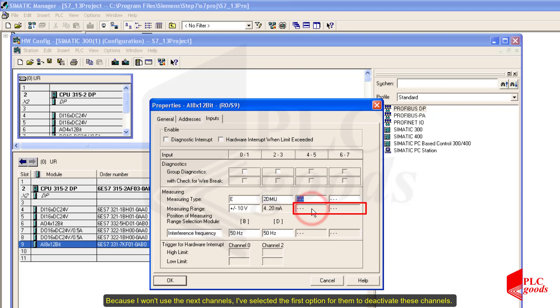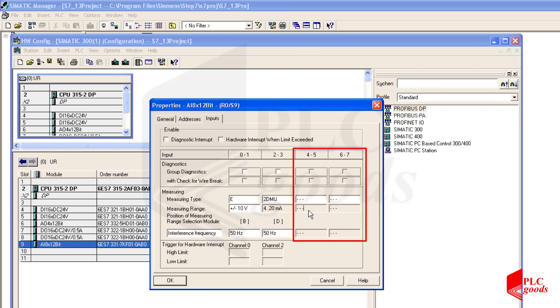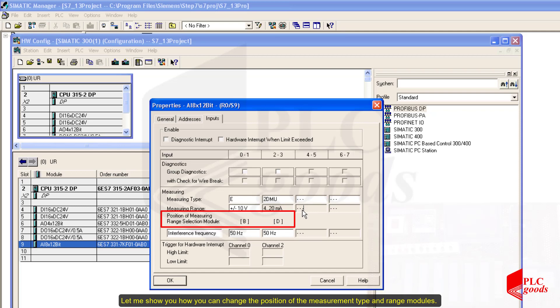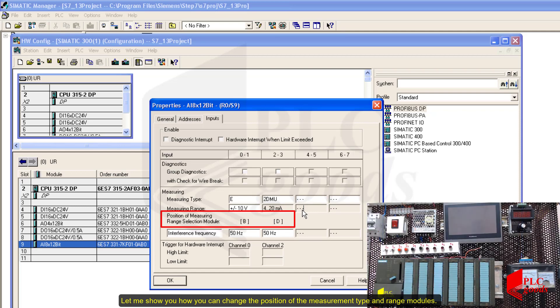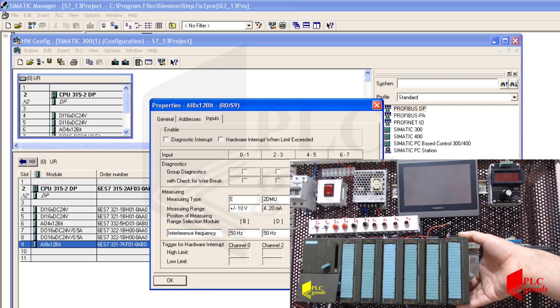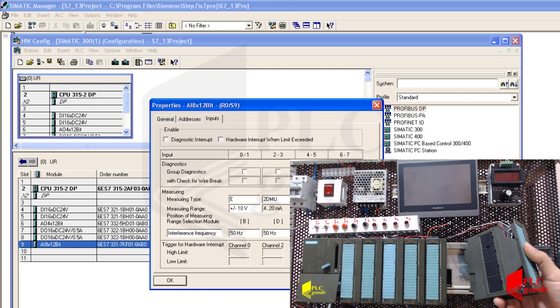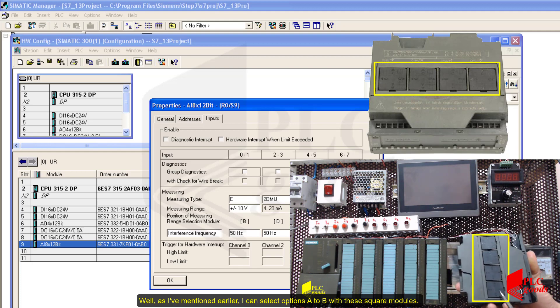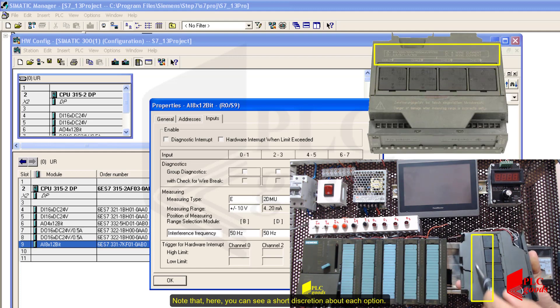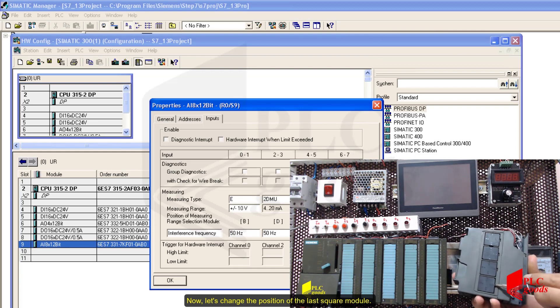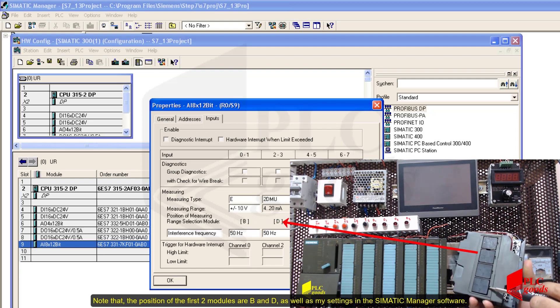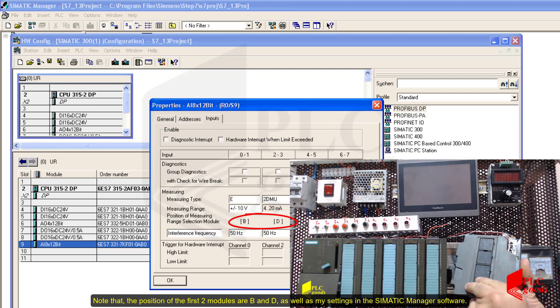I also need to select the measurement type on the analog module physically. I can select options A to D with these square modules; a short description about each option is printed on the analog module. Let's change the position of the last square module. Note that the position of the first two modules are B and D, which matches my settings in the Simatic Manager software.